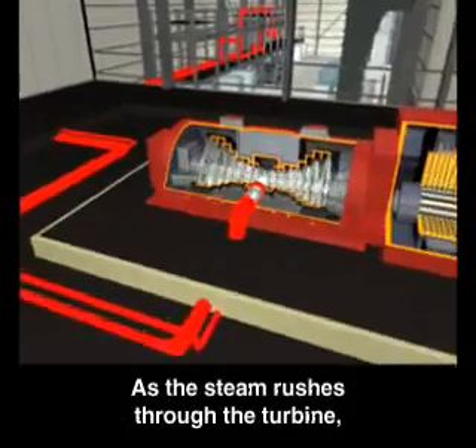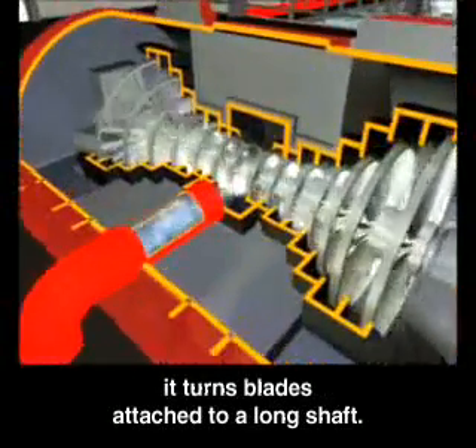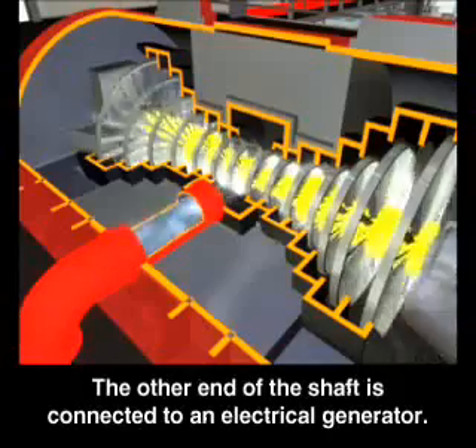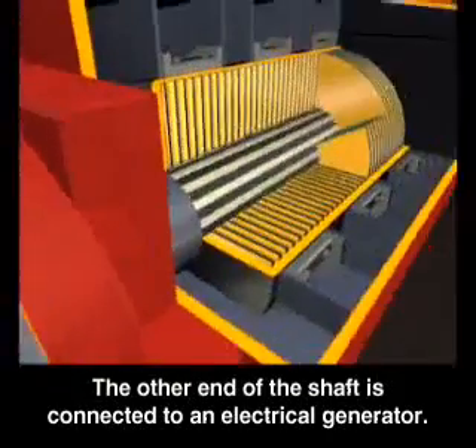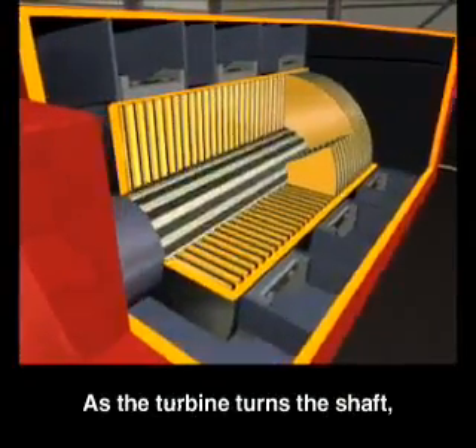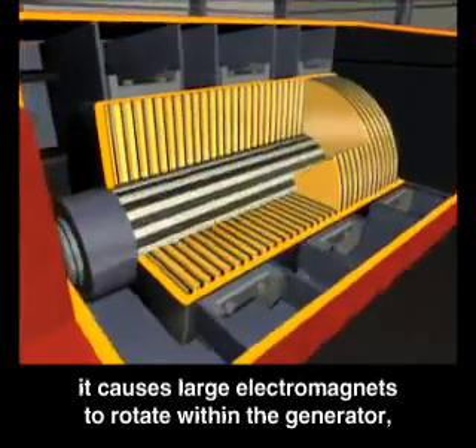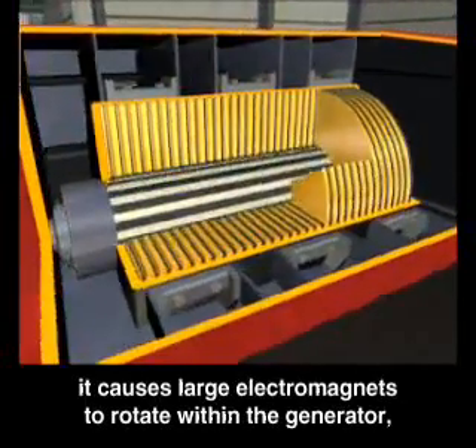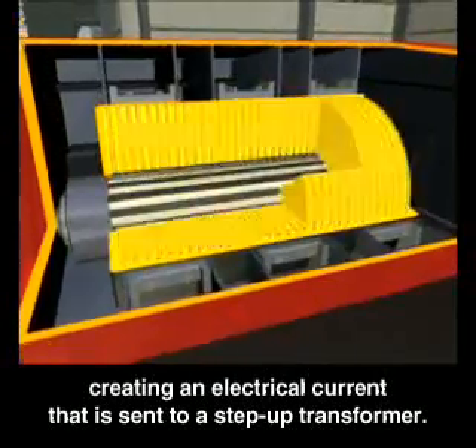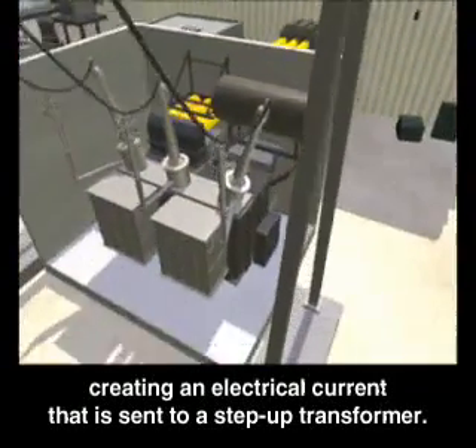As the steam rushes through the turbine, it turns blades attached to a long shaft. The other end of the shaft is connected to an electrical generator. As the turbine turns the shaft, it causes large electromagnets to rotate within the generator, creating an electrical current that is sent to a step-up transformer.